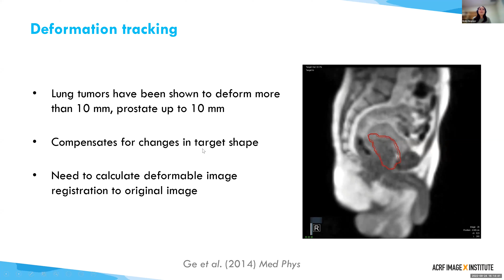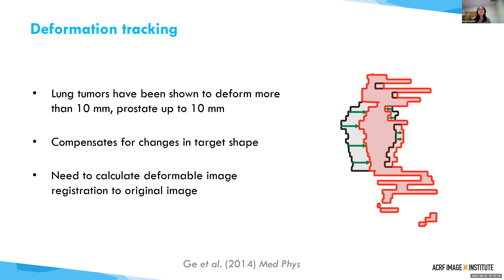So again, we can use MLC tracking to correct for this. We can actually deform the planned aperture shape according to the deformation we're observing in the target. So this really highlights one of the advantages we can get with MLC tracking, where we have the freedom to actually reshape the radiation field as we're delivering it to correct for this motion.